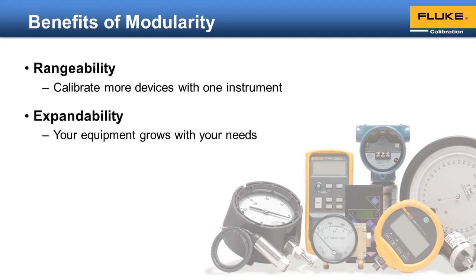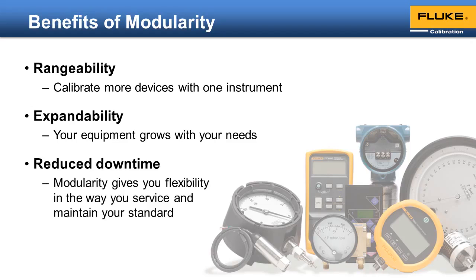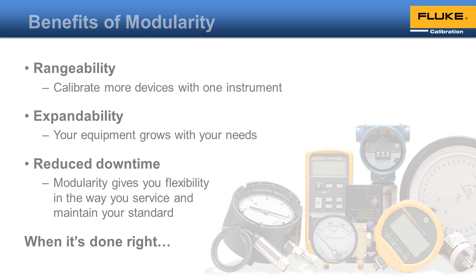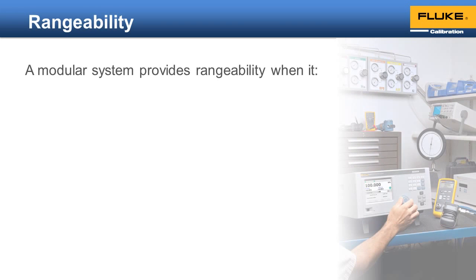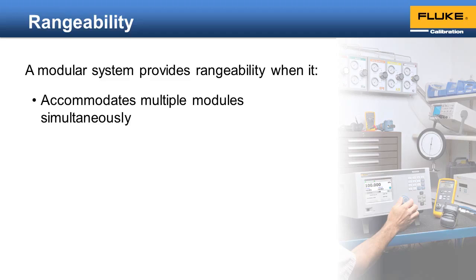And finally, modularity can reduce your downtime. It gives you flexibility in the way you service and maintain your pressure standard. Of course, you only see these benefits when modularity is done right. Not all pressure controllers that are described as modular will provide these benefits. It has to have a proper design. A modular system lets you calibrate a wide range of products when it accommodates multiple modules simultaneously. If it only supports 1 or 2 modules, then your range of coverage will be compromised.